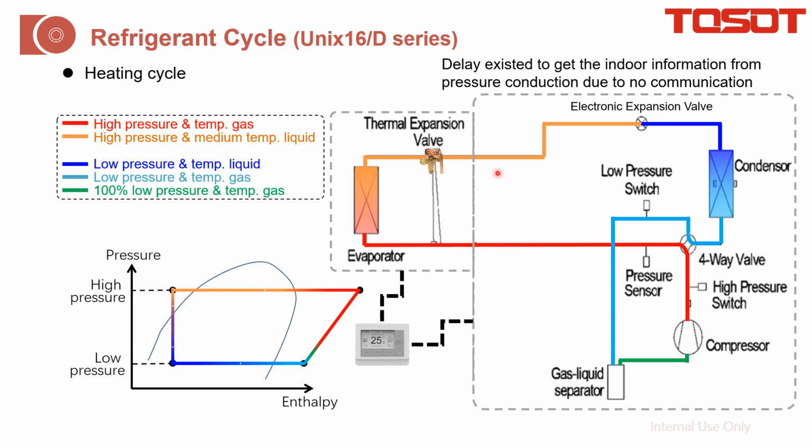As for the liquid pipe, just like what I said, in cooling mode, this part, even with this heat, is a benefit to the capacity. We don't require insulation for cooling. And in heating, this part is hot, which is also warmer than the outdoor ambient. So if you don't want to sacrifice this part, it also requires insulation. So to summarize, in cooling only, this one doesn't need insulation, but in a heat pump system, here we require the insulation.